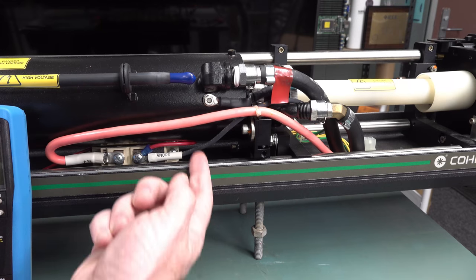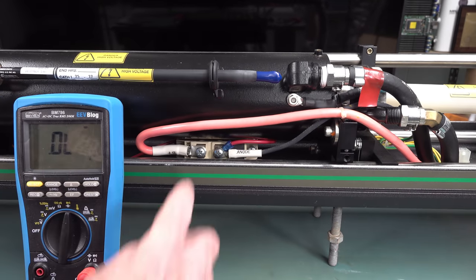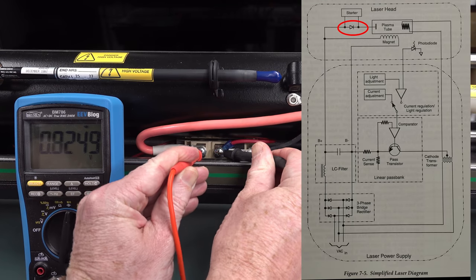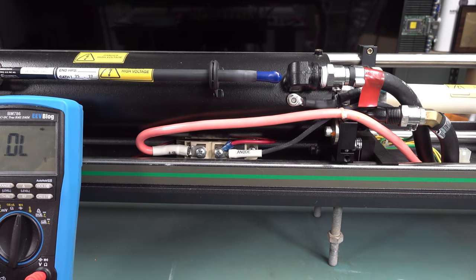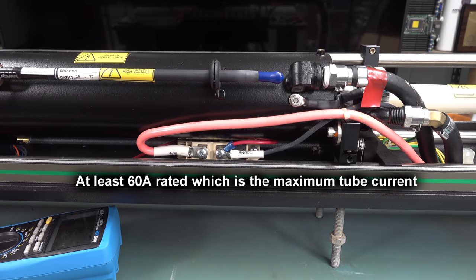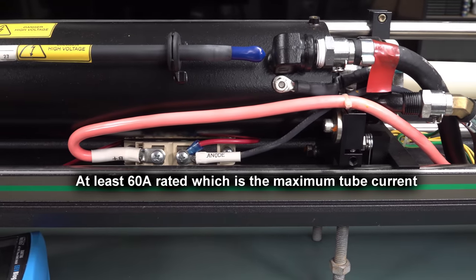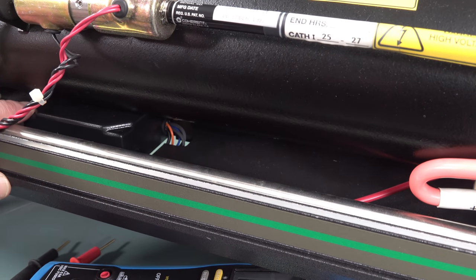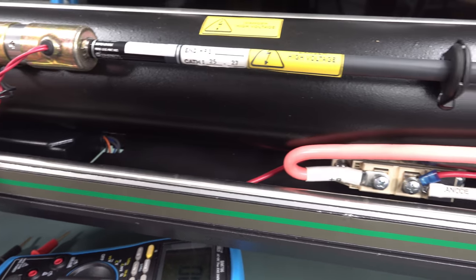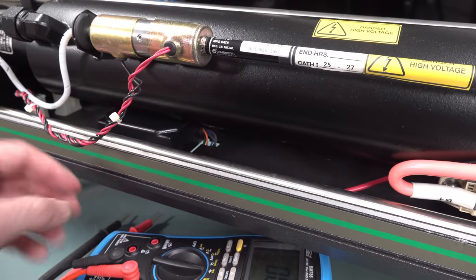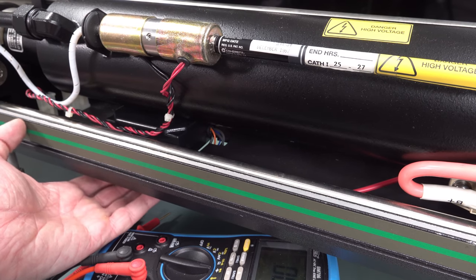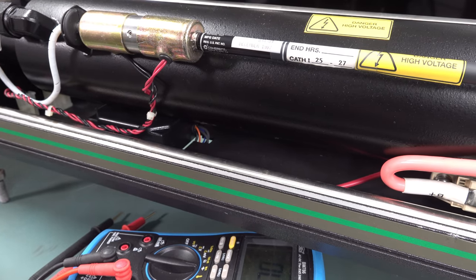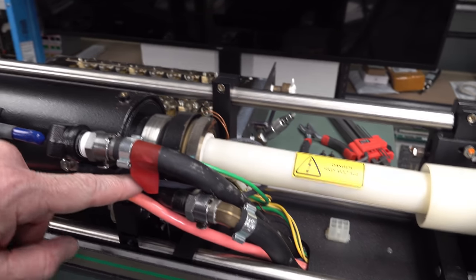And then the big red cable in here. That is for the anode. And that's labelled B+. And then it goes off here. What we've got here is a diode, eh? If we... Do we have the right direction? We do. There you go. It's a diode. Yeah, so that'd be a big, special doodad diode in there. High voltage jobby. And you can see, there's a red wire tapping off there. And that goes into this box down here, which I believe would be the starter for this thing. So that would help give it the kick required to actually start this thing off. And then the cable from this starter actually goes off to the monitoring board on the bottom. So yeah, how that all works.